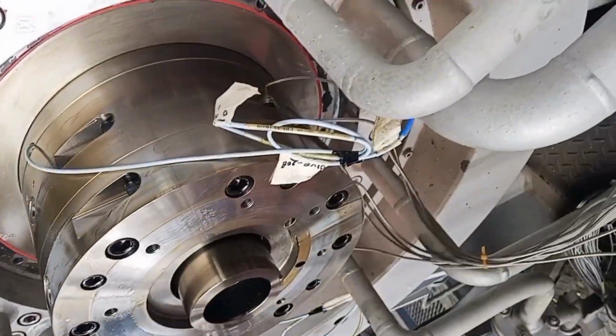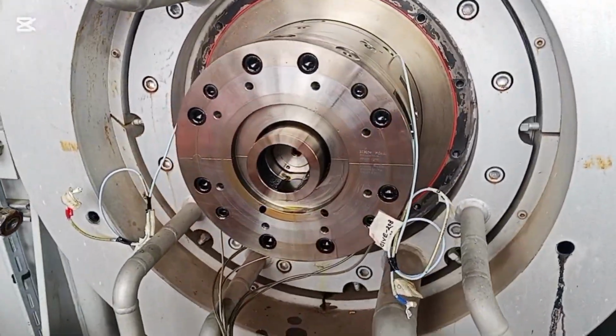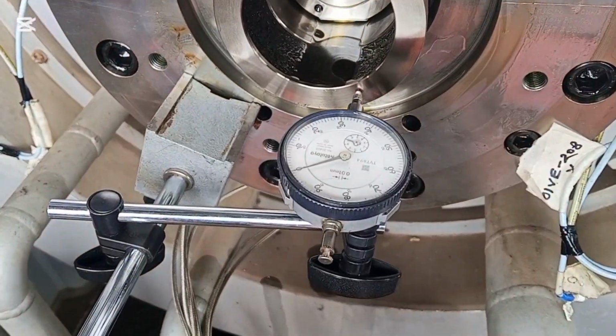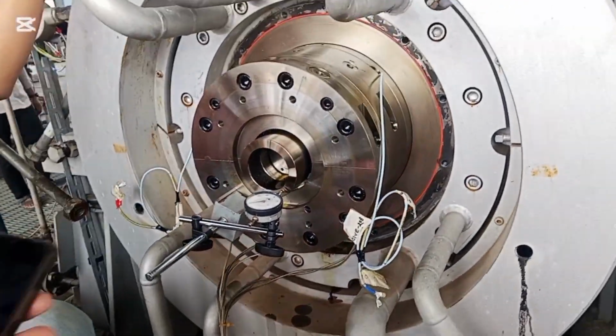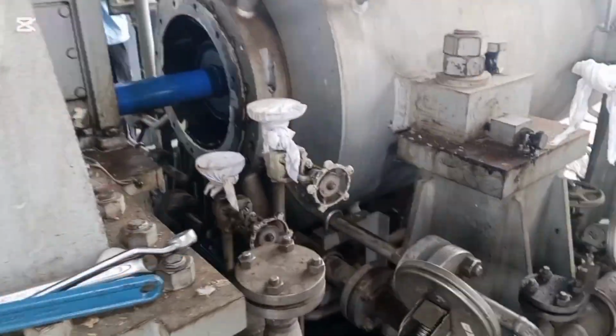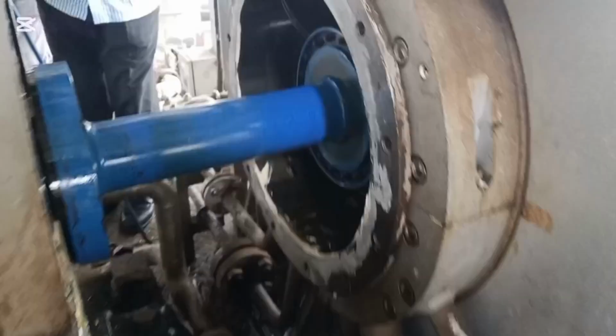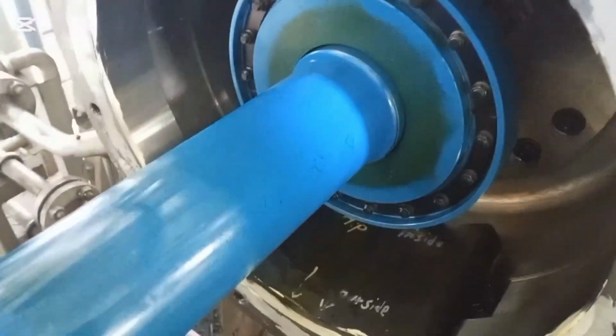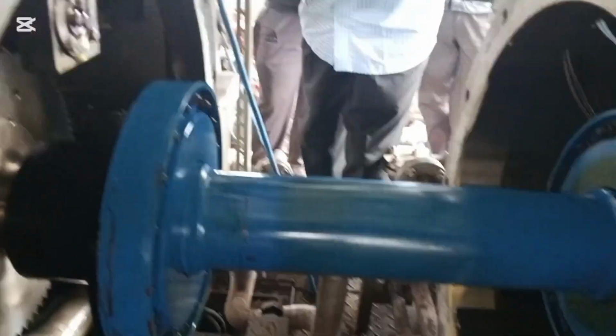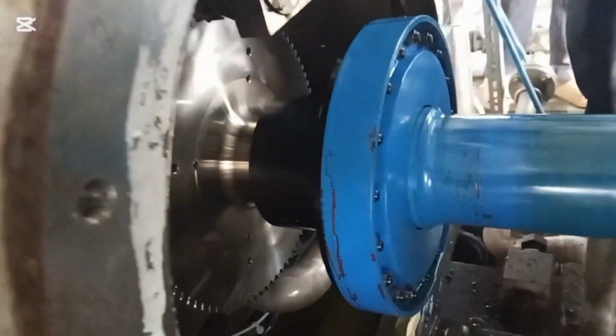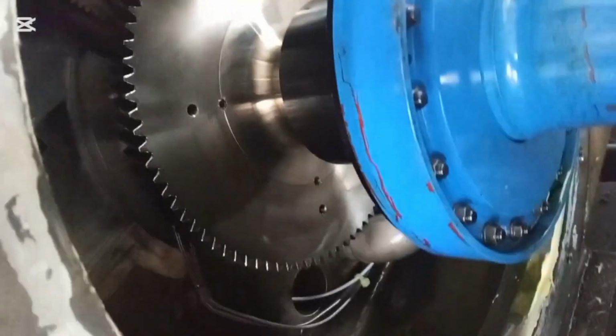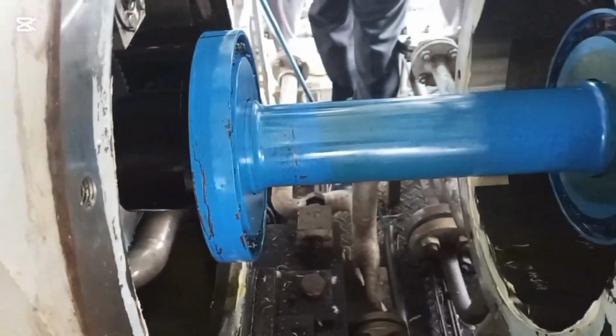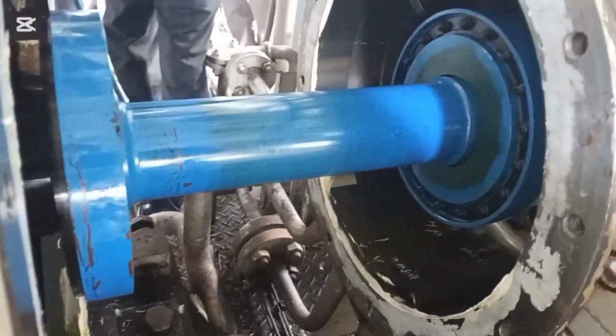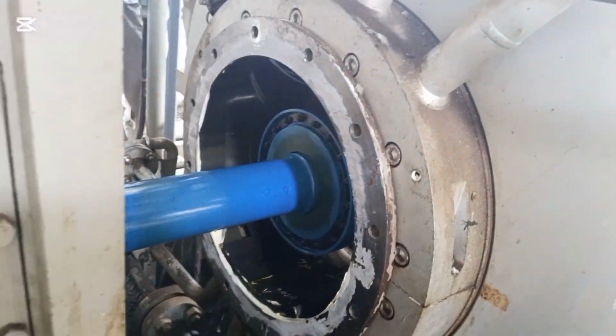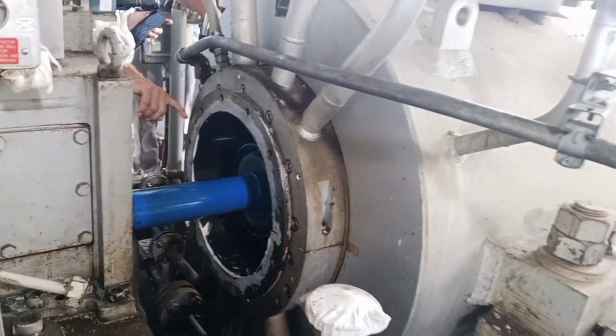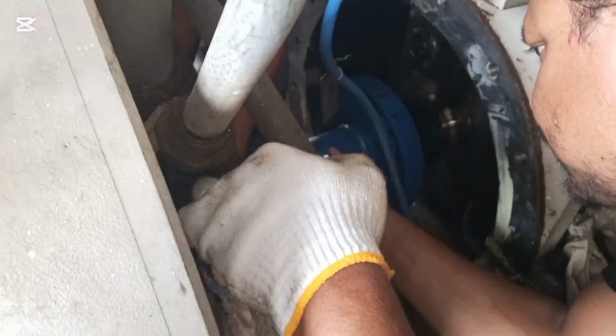We need to follow the drawing and its sequence for proper maintenance works. And then setting the special tool for pulling the dry gas seal, and after that removing the dry gas seal assembly. After disassembling the dry gas seal, we found some dust particles as well as some black parts, and we need to change this with a new one, and the new seal is available in our store.